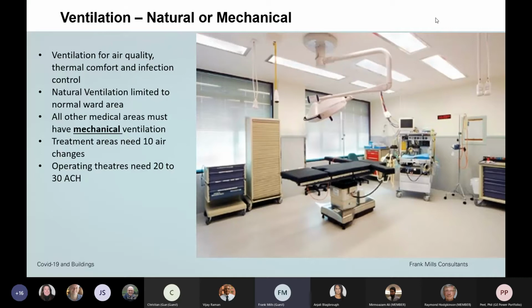In the UK, we do use natural ventilation, but we limit it really to ward areas, which for a typical UK hospital could be up to half the rooms in the hospital. But anything where we're doing clinical or medical work would be sealed and mechanically ventilated, and the HVAC systems would then have these features I talk about. Even the naturally ventilated areas have to have effective ventilation, which would reduce any COVID risk.